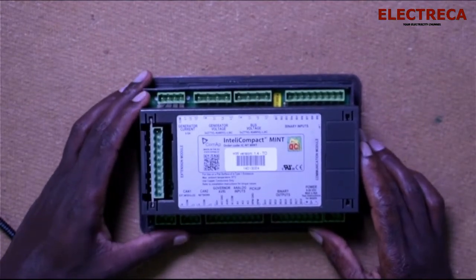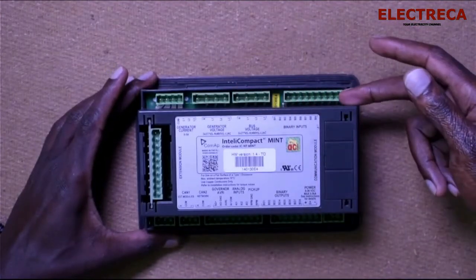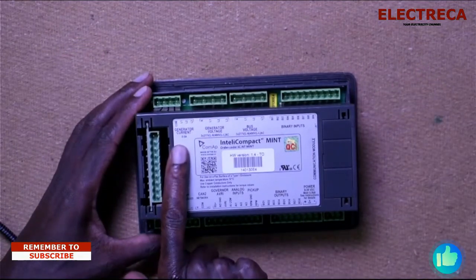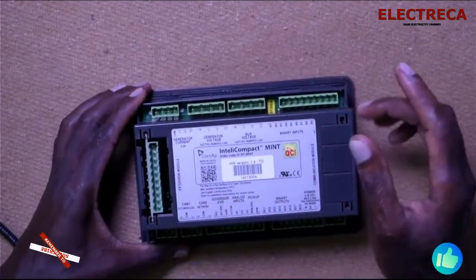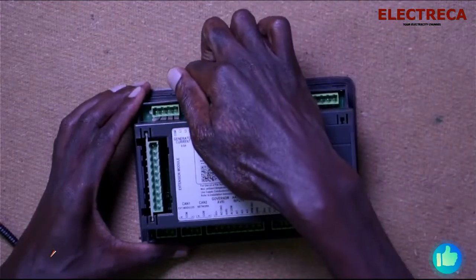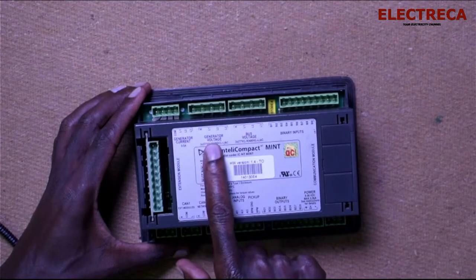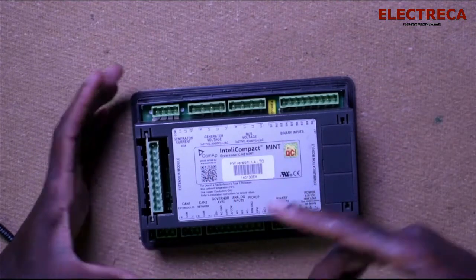On the back you can see all these sockets. Each socket carries something. On this side we have generator current, which are the CTs that feed in here. There are three CTs, so each socket has four terminals — one per CT phase — and the fourth terminal is grounded. Then you have generator voltage, which is line to line: neutral, L1, L2, L3.